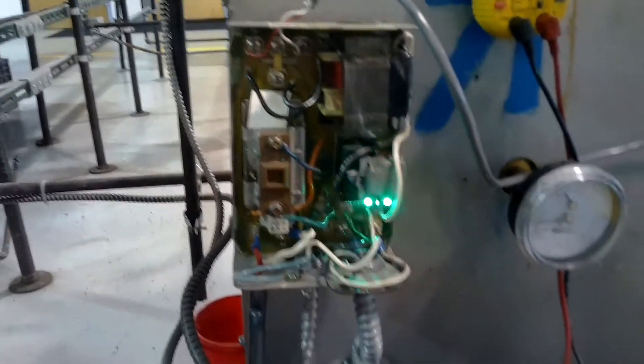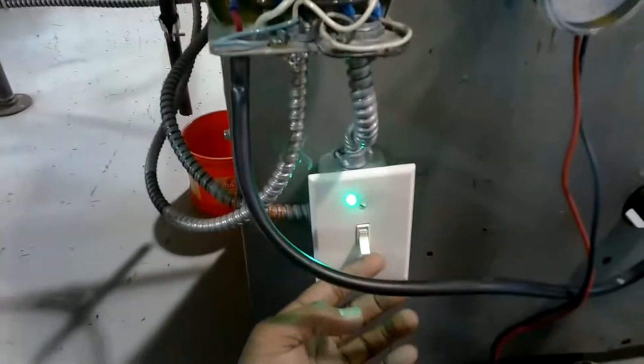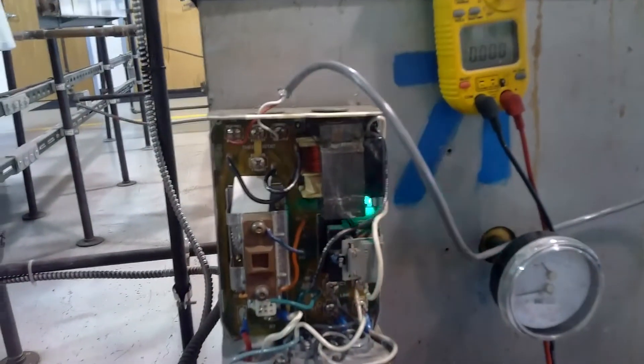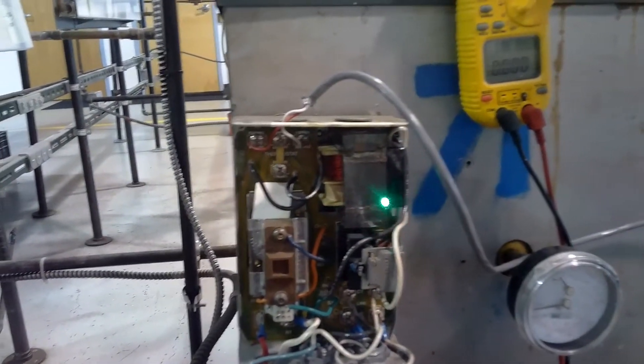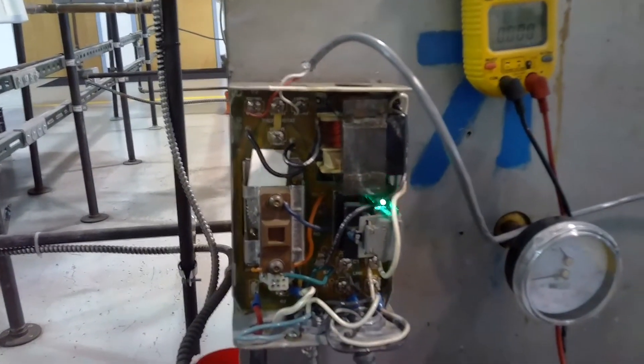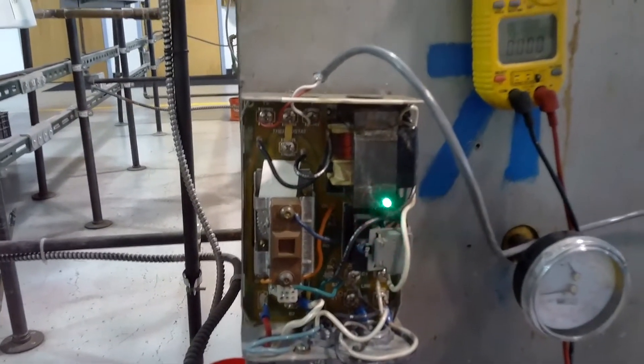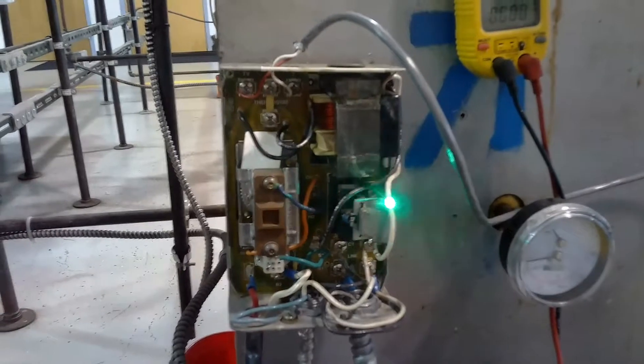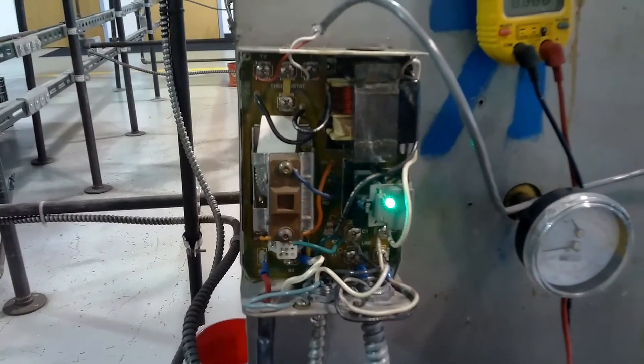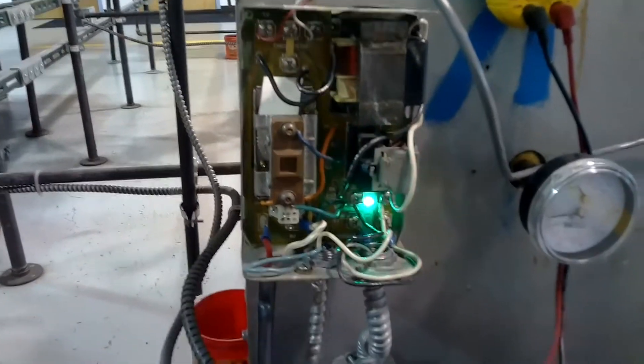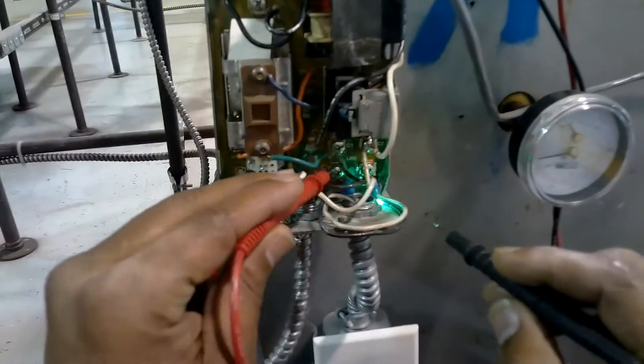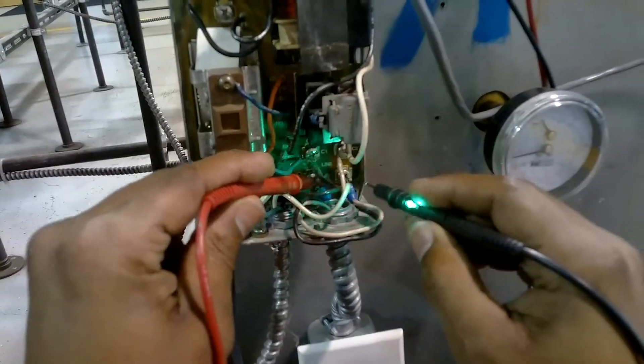I'll turn on my service switch. I'm already calling for heat, so I'm going to check 120 voltage going into my aquastat at line one and line two.